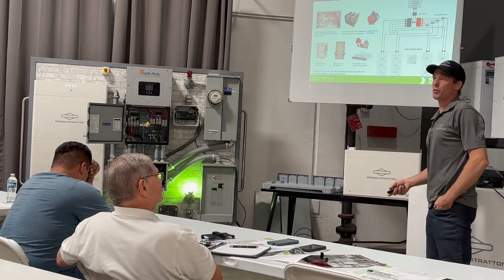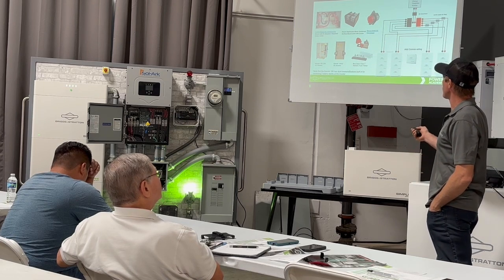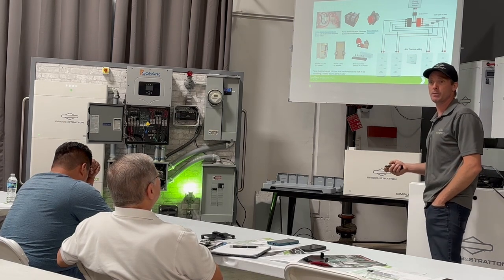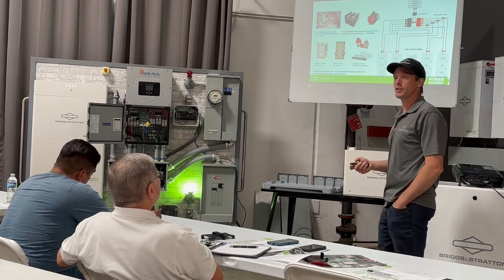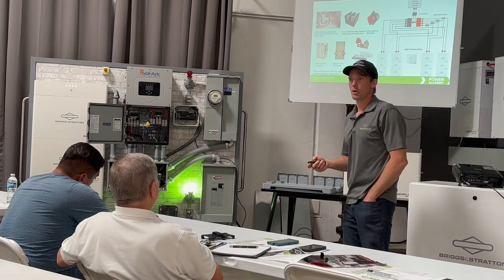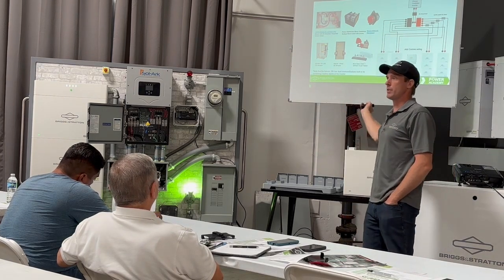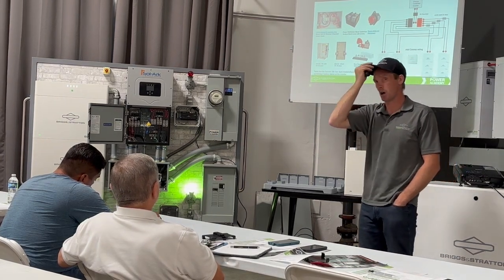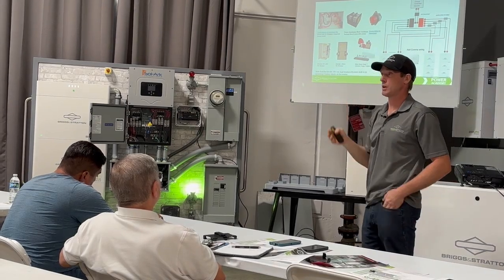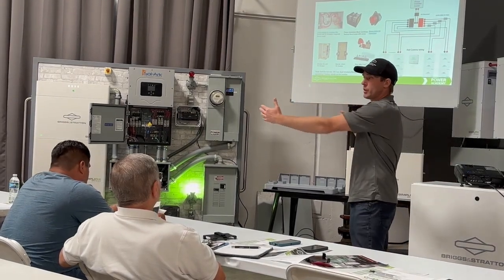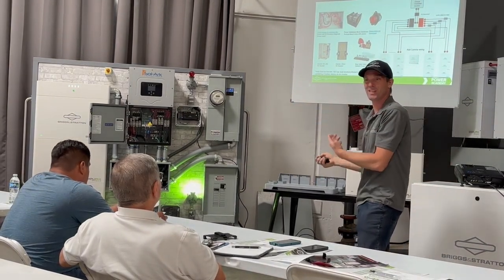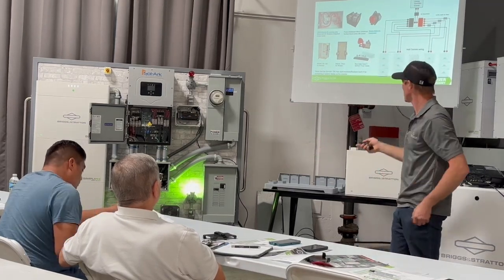So that's one option for outdoor. The common one everybody uses is the MidNite 1000 amp combiner. The 4 stacks in my van going to the install this week use a 1000 amp combiner. It's 24 inches by 36 inches tall, so it takes up a decent amount of wall space.